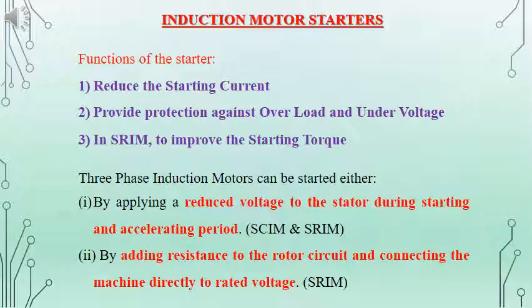So the starters can be divided into two categories, where it will be applying a reduced voltage for starting as well as accelerating. This type of starter can be used for squirrel cage induction motor as well as slip ring induction motor. And in the second category, we can add additional resistances on the rotor circuit. That is possible in the case of slip ring induction motor alone, which can even improve the starting torque.